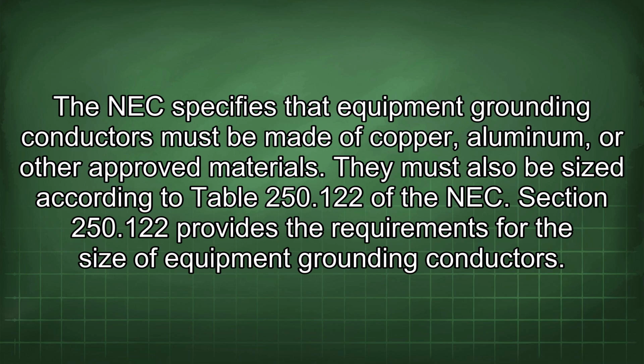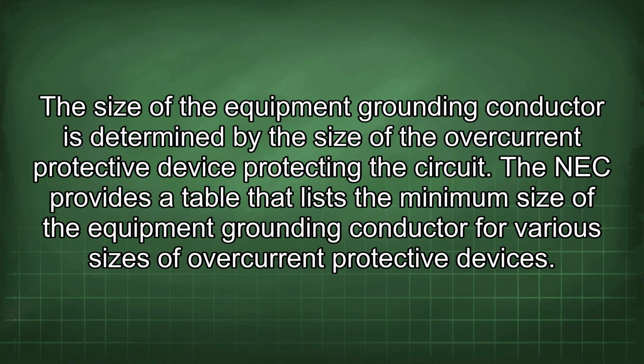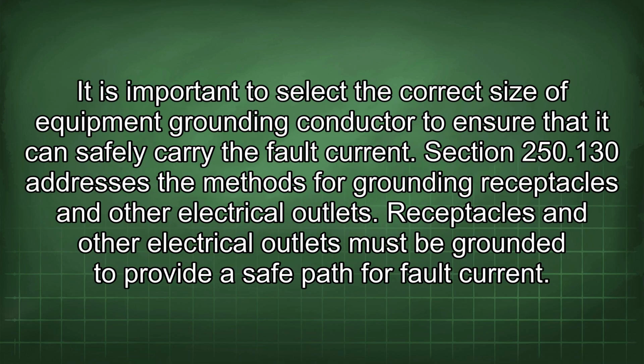Section 250.122 provides the requirements for the size of equipment grounding conductors. The size of the equipment grounding conductor is determined by the size of the overcurrent protective device protecting the circuit. The NEC provides a table that lists the minimum size of the equipment grounding conductor for various sizes of overcurrent protective devices. It is important to select the correct size of equipment grounding conductor to ensure that it can safely carry the fault current.